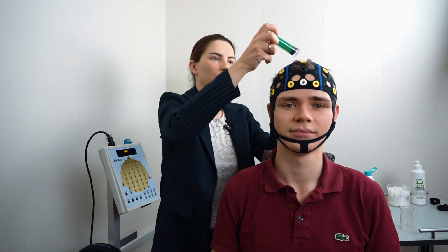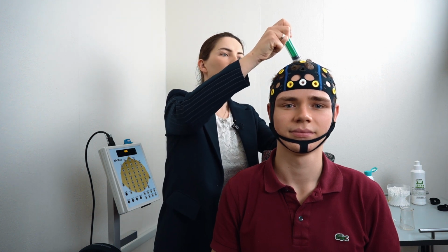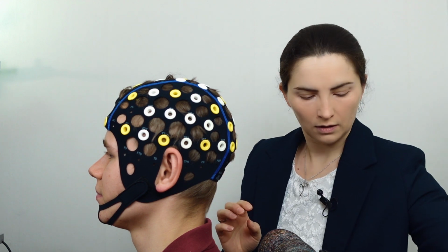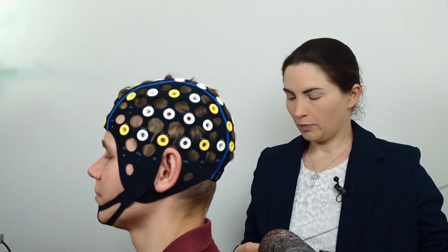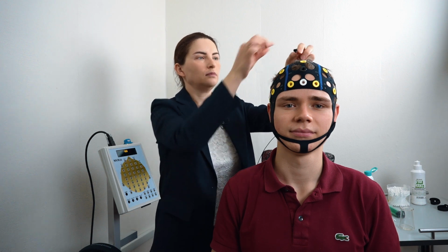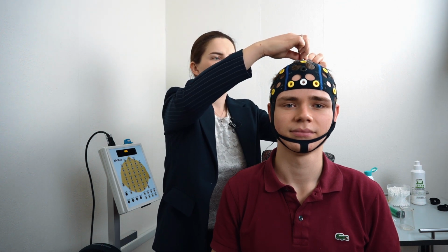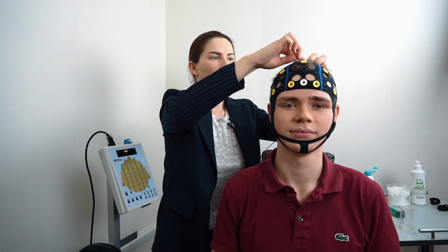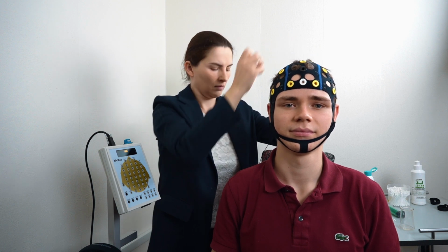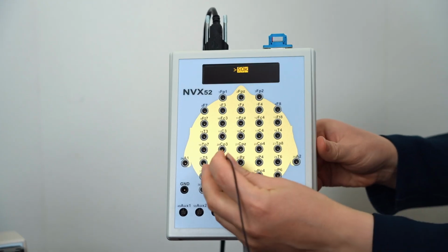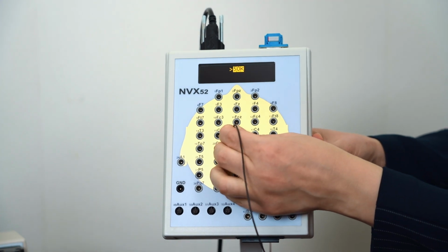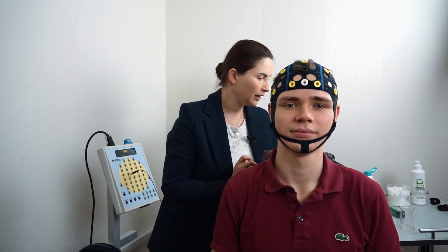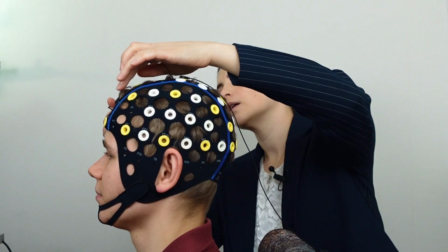Add an electrically conductive gel. Then we fix the silver chloride electrode. Now we can connect this electrode to the amplifier in the appropriate CZ connector. The next electrode we'll install will be the grounding one. We repeat all of our operations again.